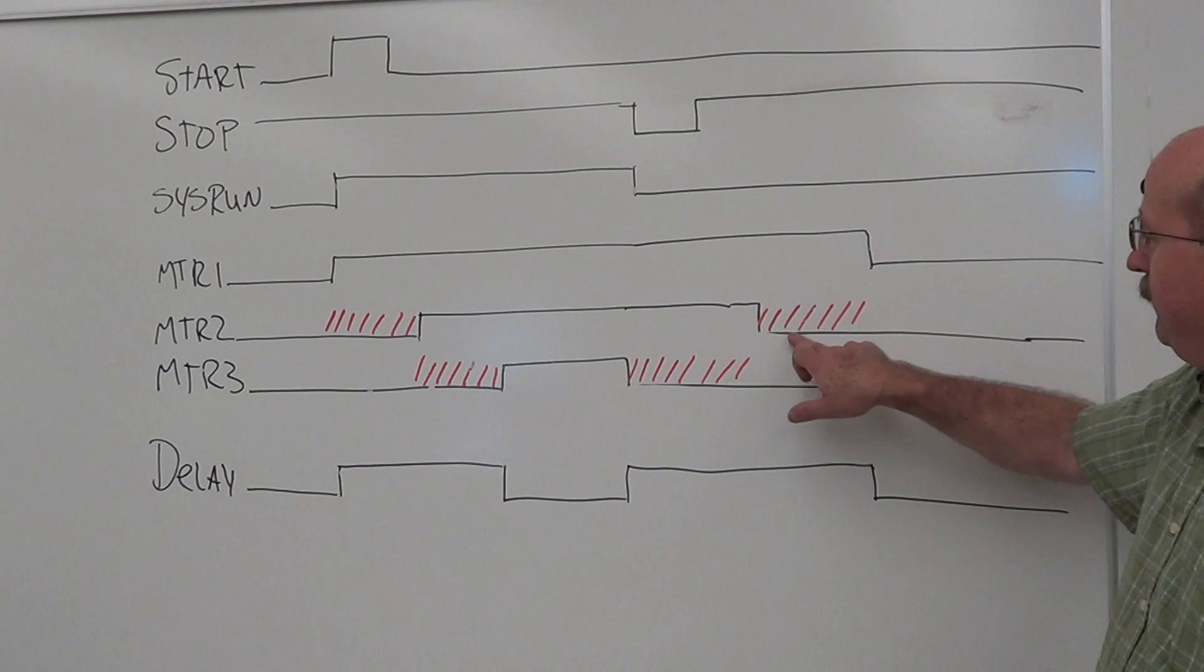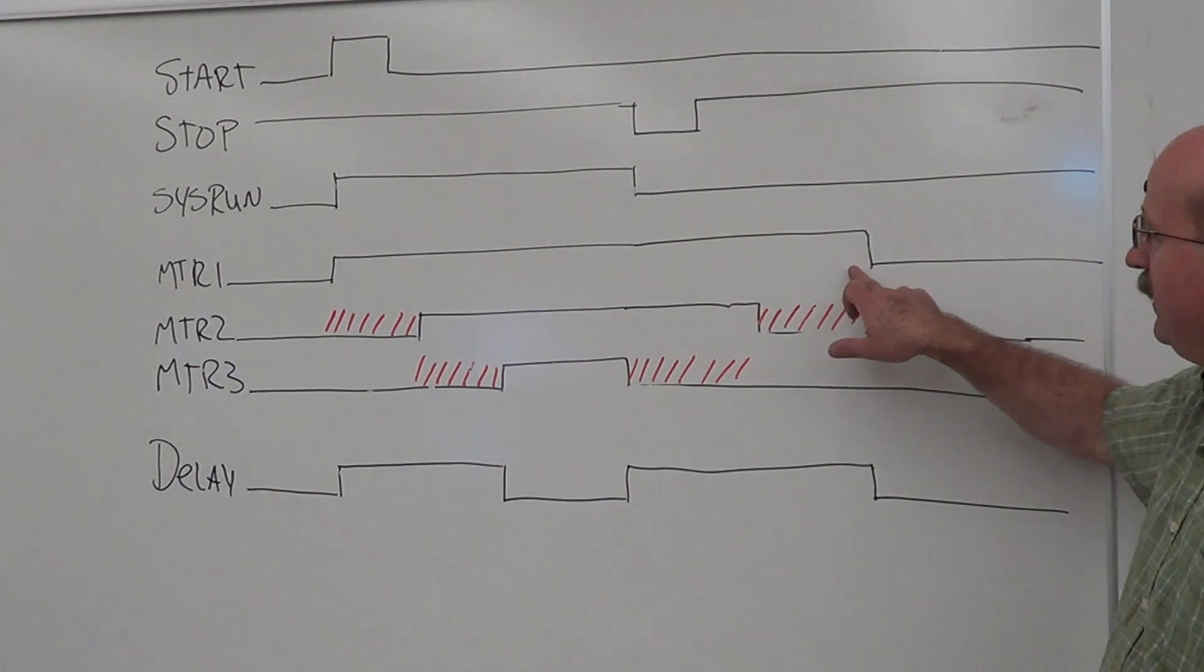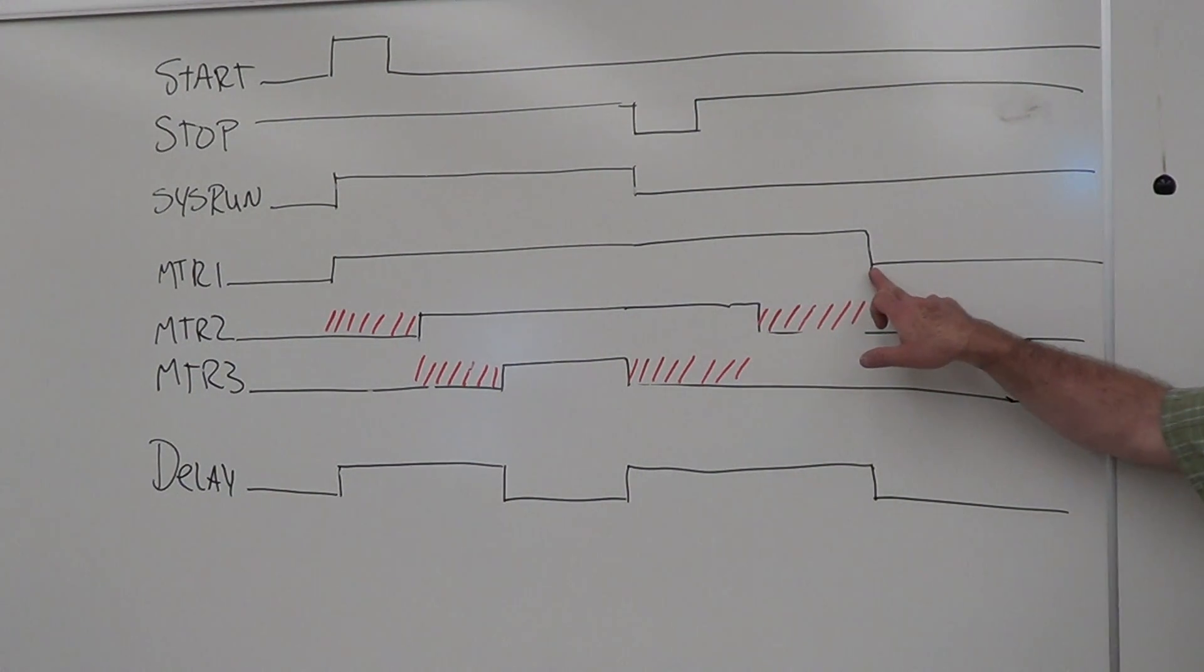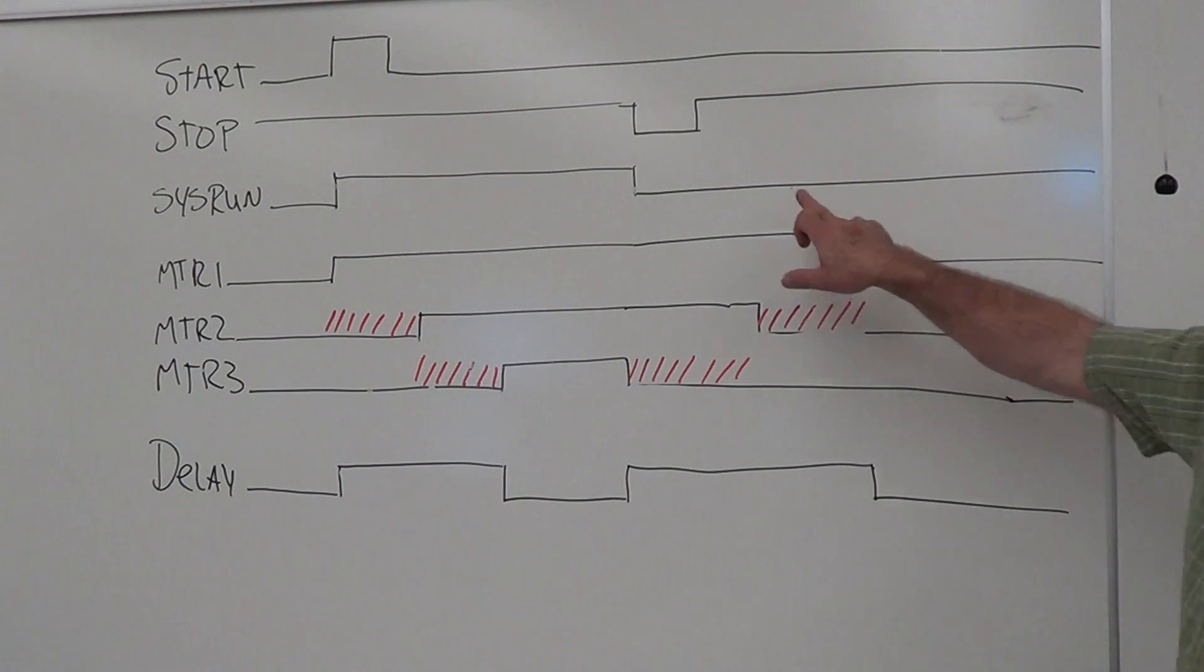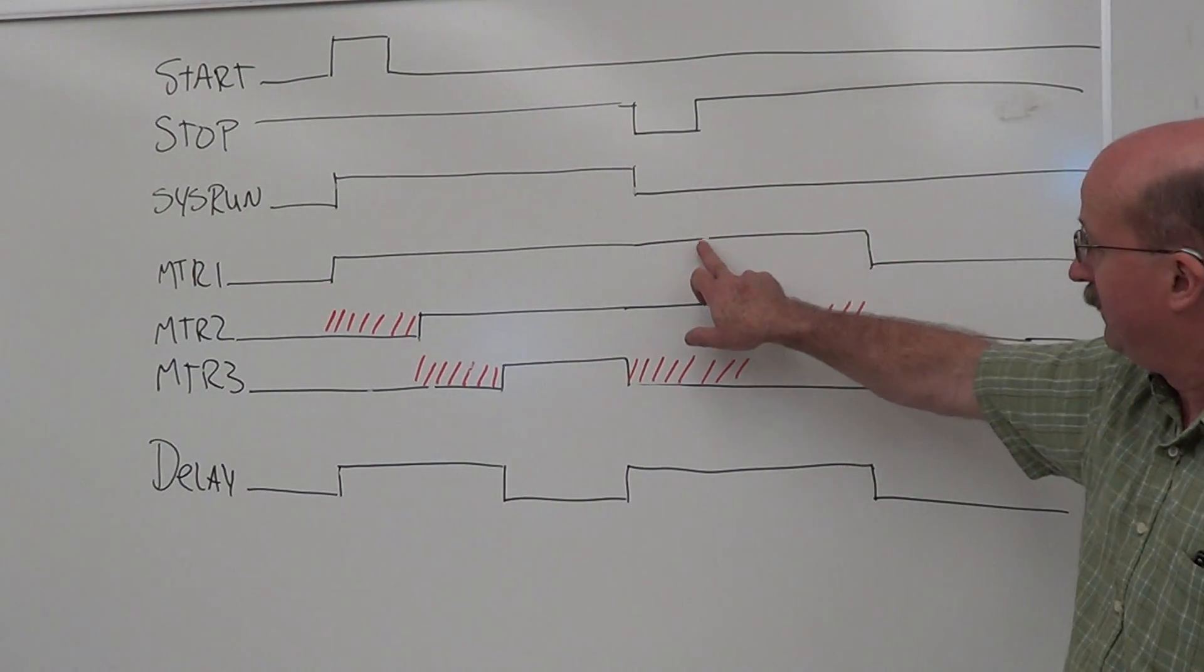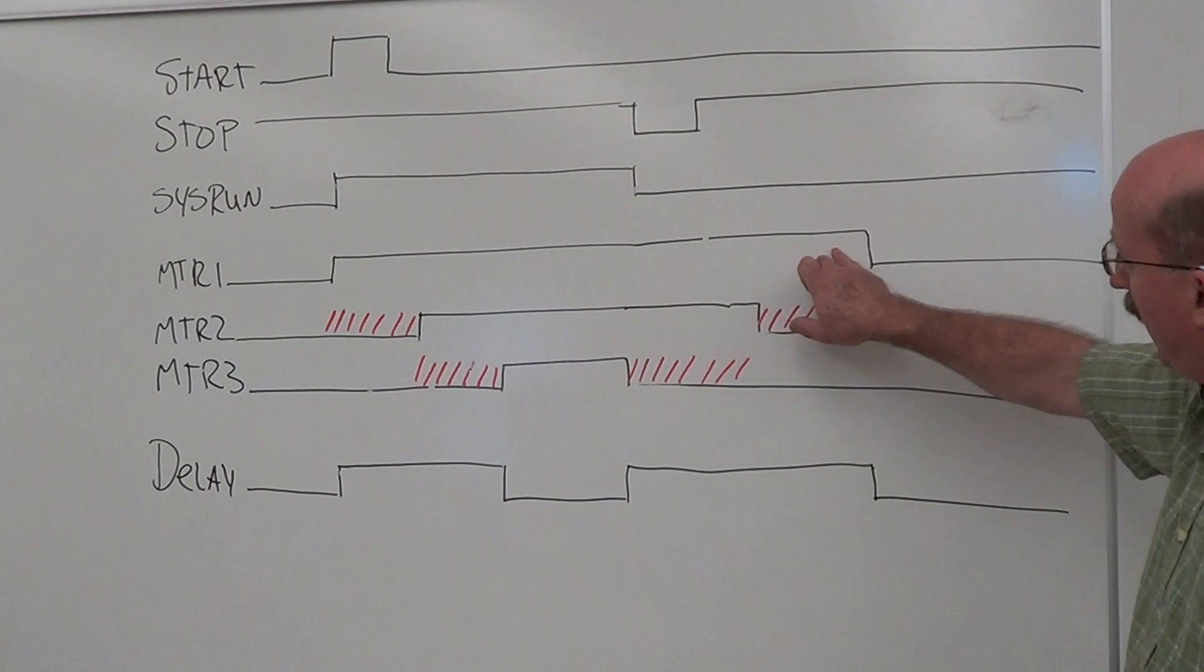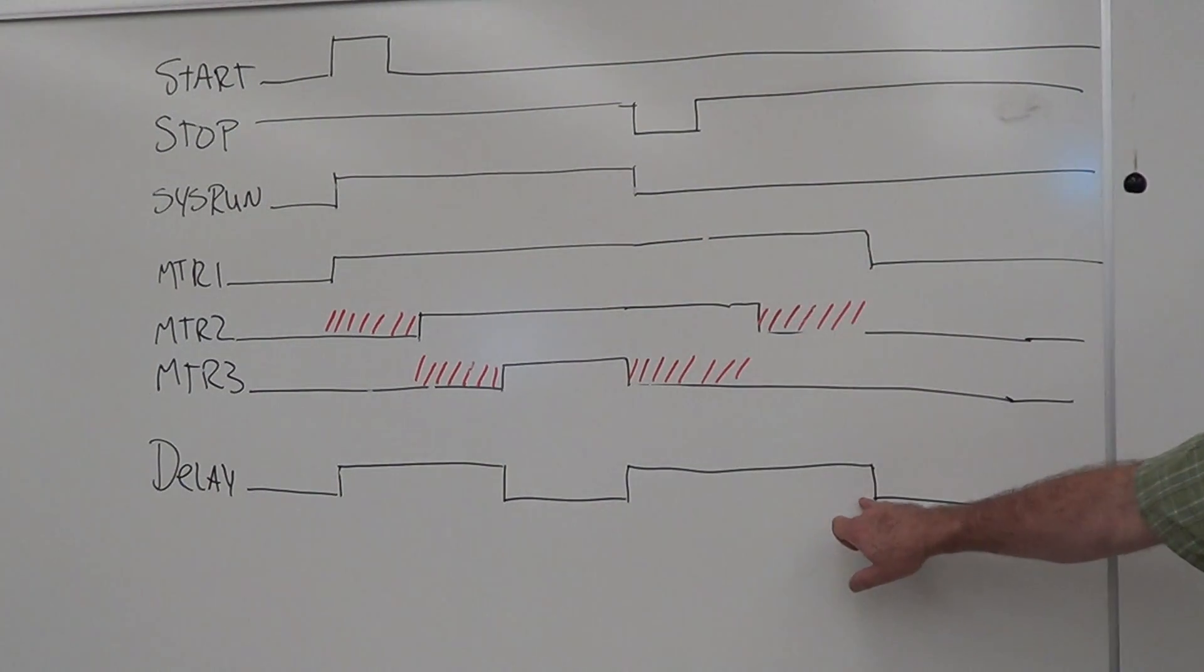Sys run turns off, motor three turns off immediately. Delay period starts for motor two, then motor two shuts off. Delay period starts for motor one, and then motor one shuts off. If sys run is off and motor one is on, that's our off-delay, isn't it?